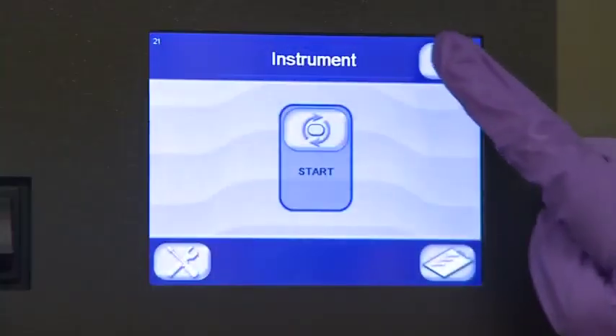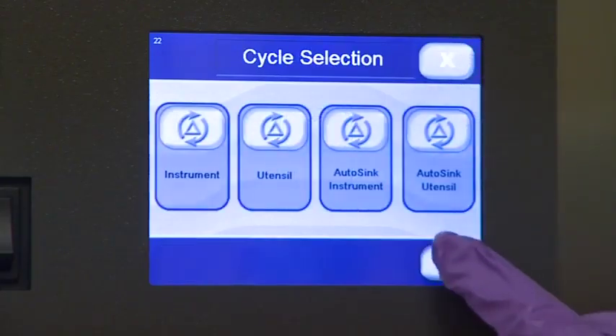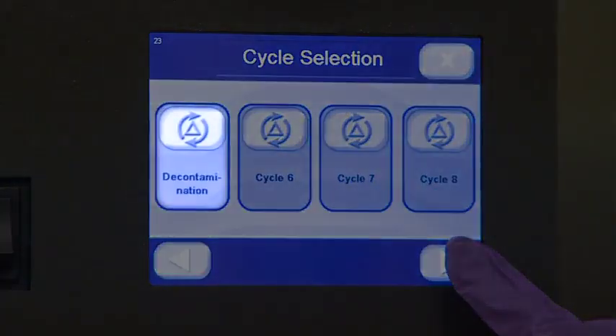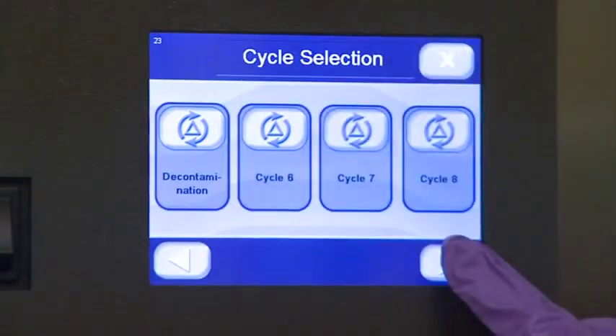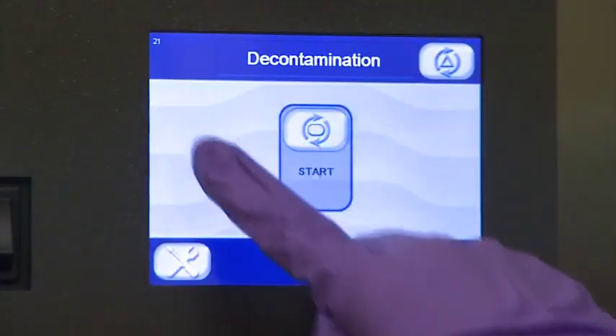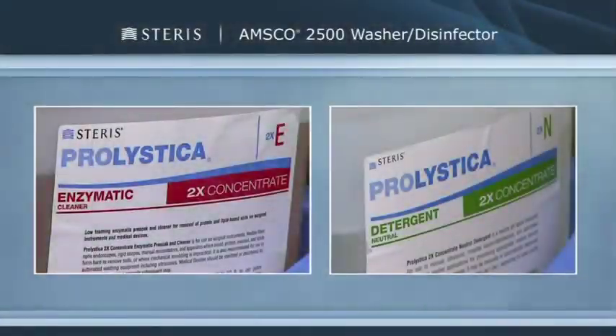Once per week, it is important to perform the decontamination of the equipment. Use the decontam cycle for this purpose. Your supervisor will schedule this step and review specific instructions. Cleaning chemistry products need replacement on occasion. STERIS recommends Prolystica 2x concentrate chemistries be used with the AMSCO 2500 washer disinfector.